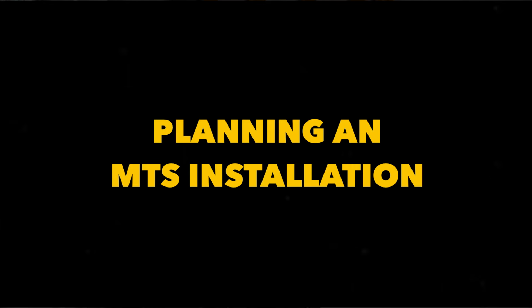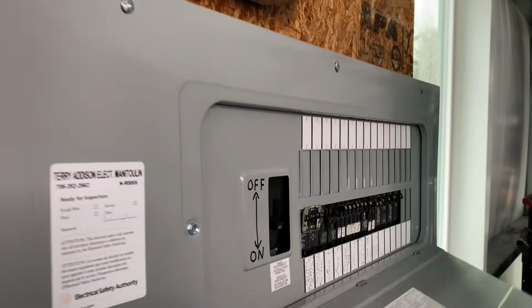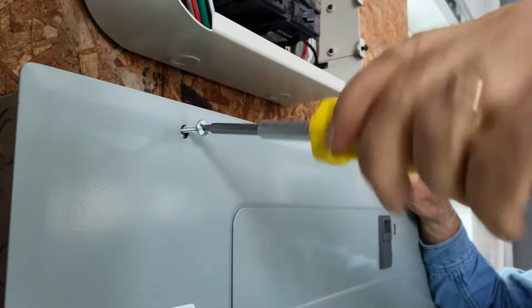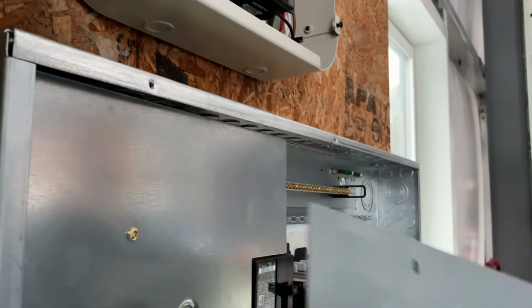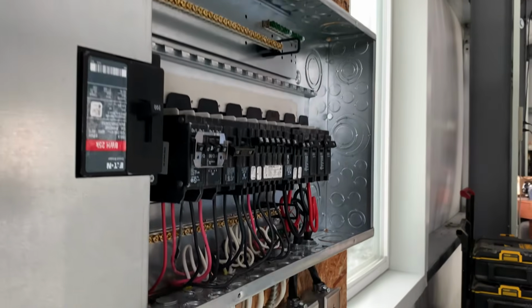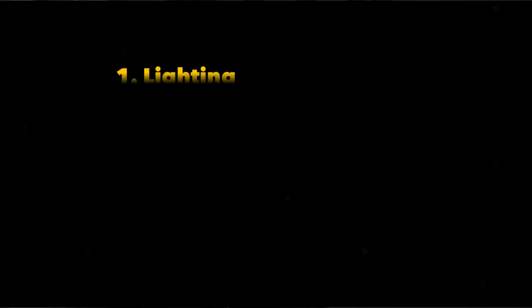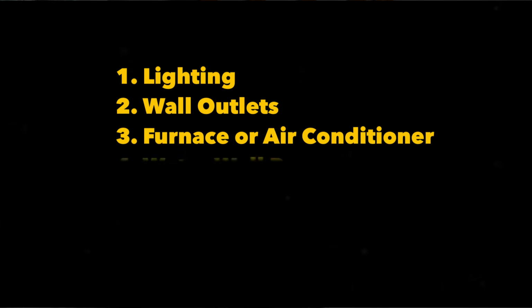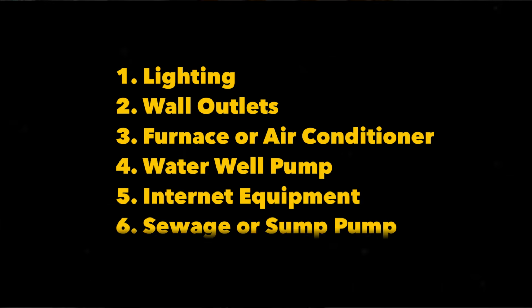Planning an MTS installation. The planning process for transfer switch installation begins by deciding which circuits you want powered by your generator during an outage and which ones you can do without. Essential circuits typically include lighting, wall outlets, a furnace or air conditioner, a water pump if you're on a well, and perhaps internet equipment, a sump pump, or a sewage pump. Many of these items don't have plug outlets, so they can't be connected to a generator using an extension cord. Sidestepping this problem is the biggest advantage of a manual transfer switch.